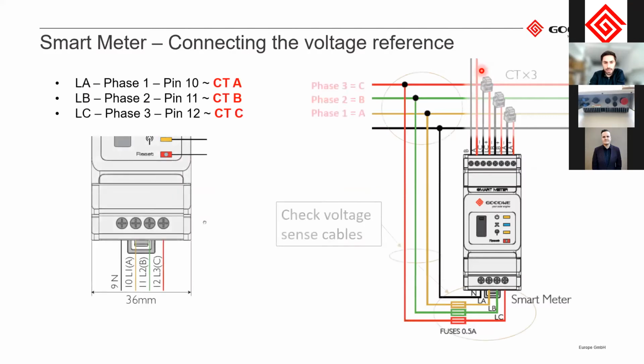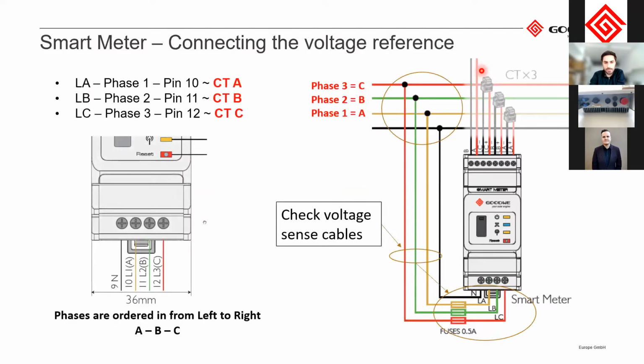On the bottom side, you will have to connect the voltage sense. And here you need to observe that they go from the other direction. So you go from left to right. So please make sure that you connect the correct voltage sense cable to the correct phase that corresponds to the correct CT.